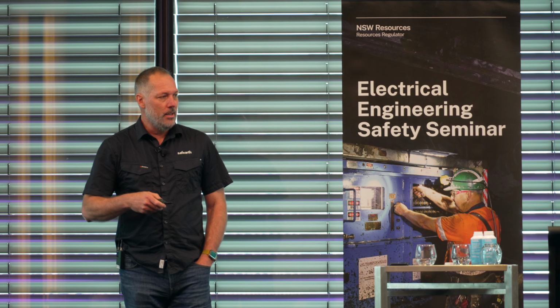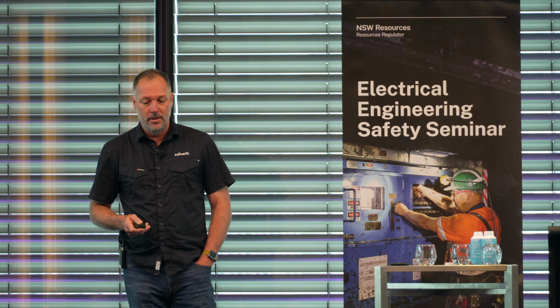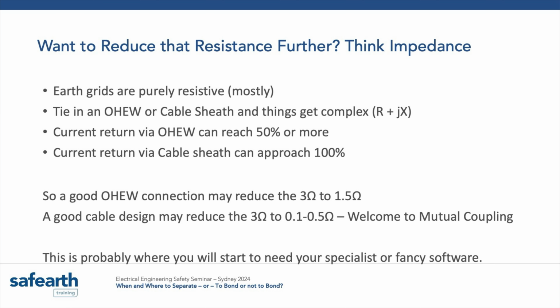If you want to go even lower, say you're on a 200 amp fault limited system up in the Hunter Valley, or even worse, if you're on Endeavour Energy 66 down around Appin, where it's not fault limited, then you might want to do something else. You might want to start introducing the idea of bonding in the DNSP earthing system, if they'll let you. I'll come back to that. That really irritates me when they don't let you.